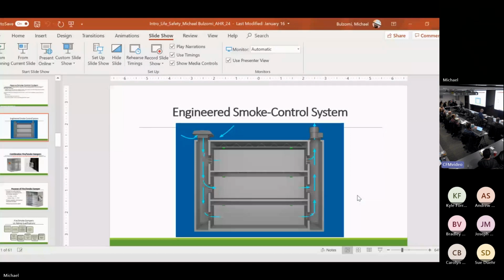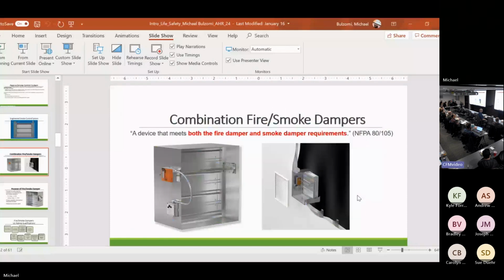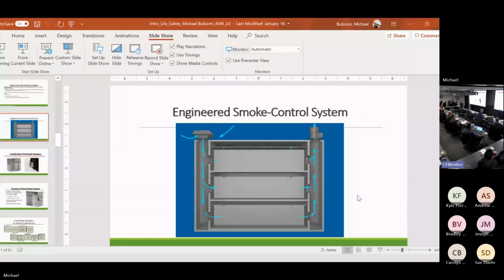This is showing a non-dedicated system, meaning that the fans are being used in everyday HVAC. That's important for code required testing purposes. That's a rudimentary smoke control system. So again, one of those dampers had a fail open. If that was a fail closed damper and it wasn't clearly labeled on the plans, that's going to be a problem sometime down in the field during installation.